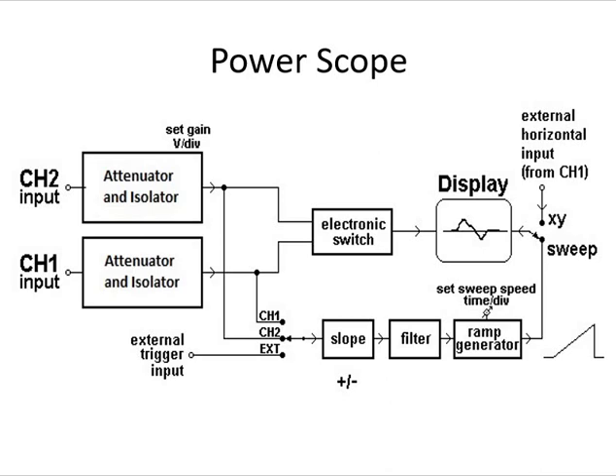The attenuator attenuates the signal and reduces its amplitude so it can be observed on the CRT screen. The isolator isolates both input terminals from external high potential and isolates the external circuit from the CRO ground. The vertical input range is from 50 mV per division to 500 V per division. The trace is switched between two channels at a rate of 100 kHz. AC mode bandwidth is 2 Hz to 15 MHz. It has wide range of measurement capability, compact design, lightweight, and high safety.